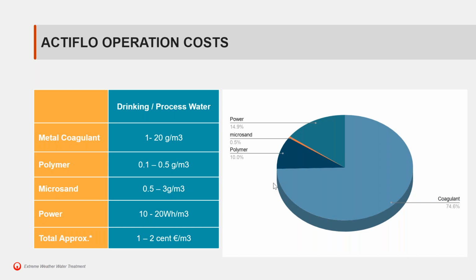A summary of the operational cost of Actiflo. I put this slide because a lot of people comment about the microsand and think it's a tremendous part of the cost. In fact, it isn't at all. Microsand is readily available, and in terms of the global running cost of an Actiflo, it only accounts for around 1%, even 0.5% - it's minimal. The bulk of the cost is coagulant and a pH adjustment agent, like sulfuric acid. Polymer accounts for about 10%, power for about 15%, and microsand for a very small proportion.